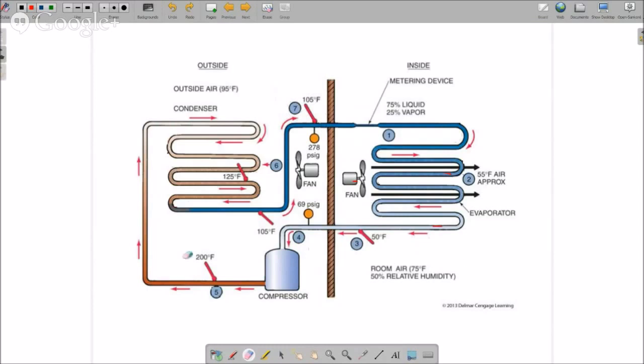The refrigerant is backed up for a longer period of time in the condenser and it sheds more heat, so your sub-cooling increases when the system is overcharged. We still have that solid column of liquid, we still hit the metering device with a 75/25 flash gas split, and then we move through the evaporator coil, changing state as it should.